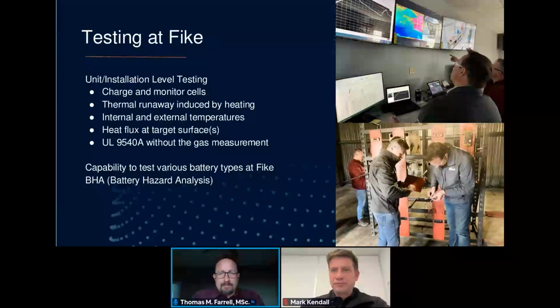At our labs, we typically focus on unit or installation level testing. So it'll either be one large module or collection of cells, or a rack populated with those modules. Within our facilities, we charge and monitor them during the test. All of our tests place our modules into thermal runaway using heating.